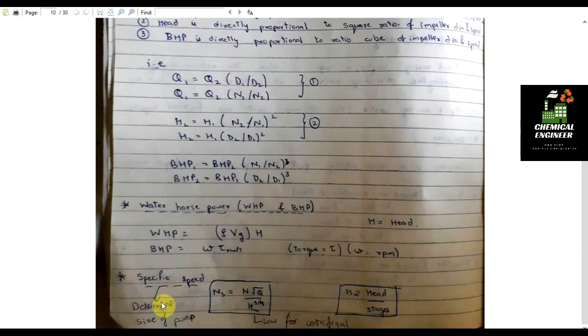We have specific speed. Specific speed is the speed up to which the centrifugal pump works well. We have a graph relating power to speed. At one point there is a maximum speed and minimum power, and that point is used to calculate the specific speed of the pump. Specific speed is N into square root of Q divided by Hm raised to 3/4. Here Hm is not the head but the head per stage. If we divide our pump into a number of stages, then Hm can be different compared to a single stage. Specific speed is used to determine the size of a pump.